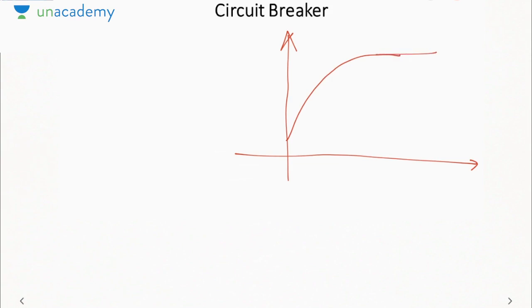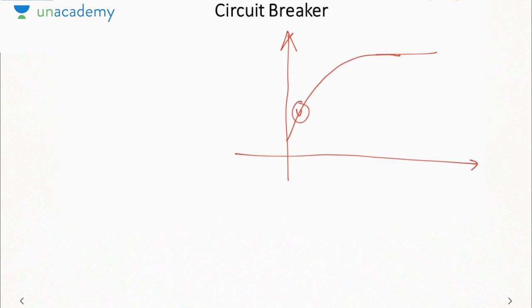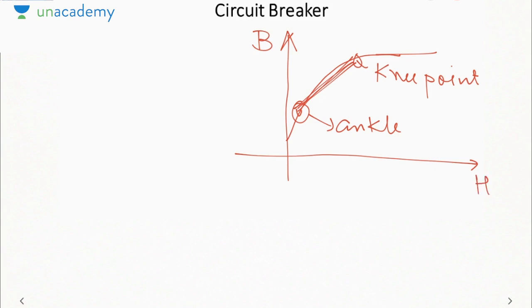Now this point here is called your ankle point. This point is called your knee point. Between the ankle point and the knee point, your characteristics are approximately linear. Linear means that B is proportional to H. Or we can say the operating force is directly proportional to current.